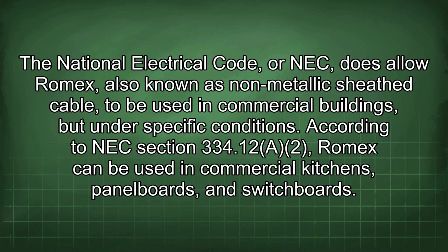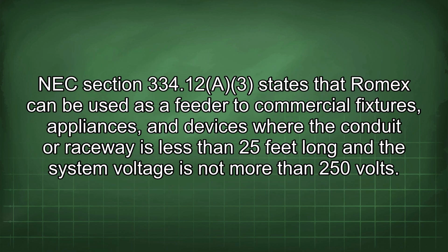The National Electrical Code, or NEC, does allow Romex, also known as non-metallic sheath cable, to be used in commercial buildings but under specific conditions. According to NEC Section 334.12(A)(2), Romex can be used in commercial kitchens, panel boards, and switchboards. NEC Section 334.12(A)(3) states that Romex can be used as a feeder to commercial fixtures, appliances, and devices where the conduit or raceway is less than 25 feet long and the system voltage is not more than 250 volts.